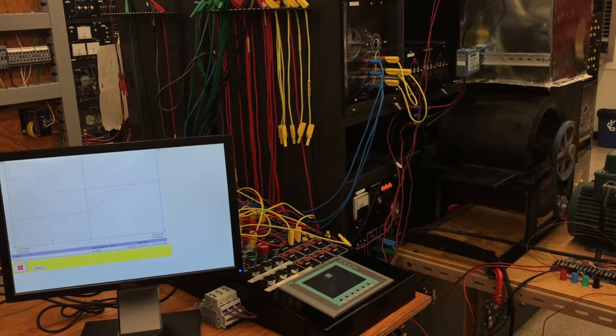As you can see, the fan's slowing down as the temperature gets close to the preset. It got a little bit above, so it added a bit more speed. But the trace is slowly getting closer to the preset value.